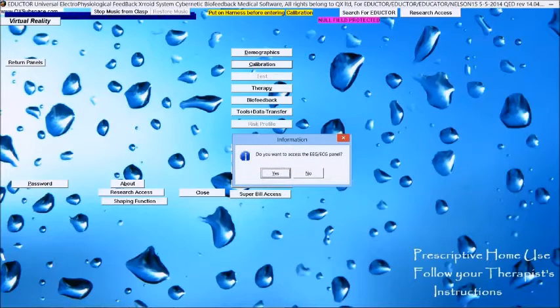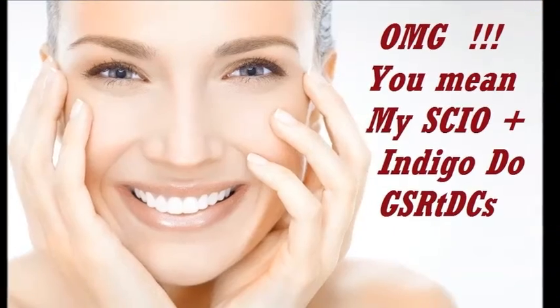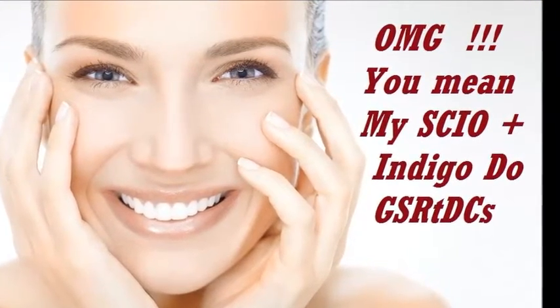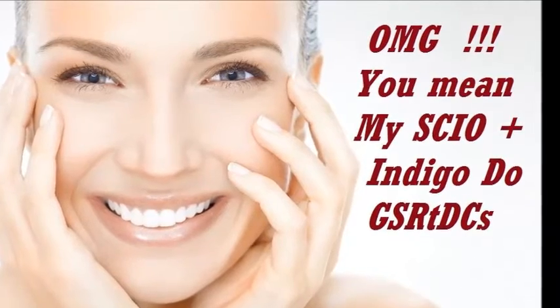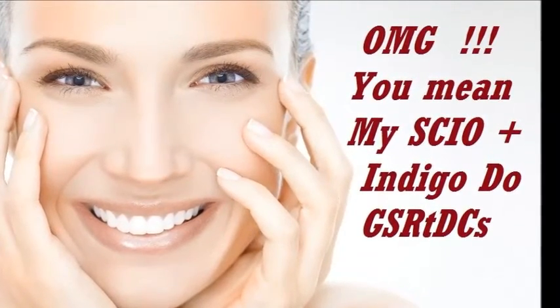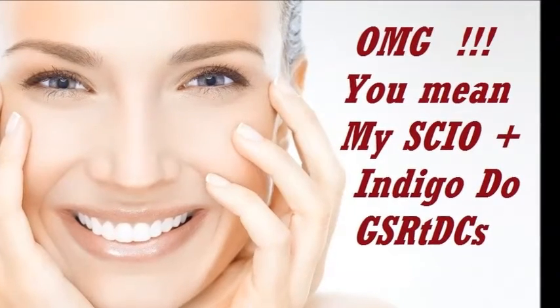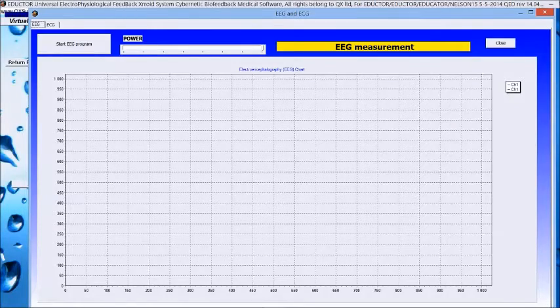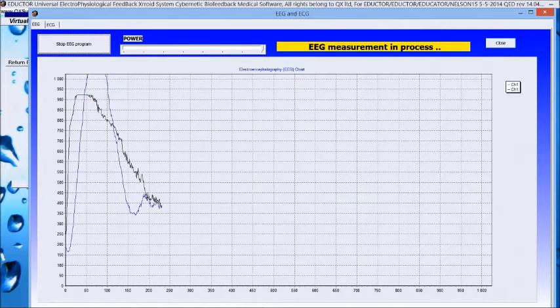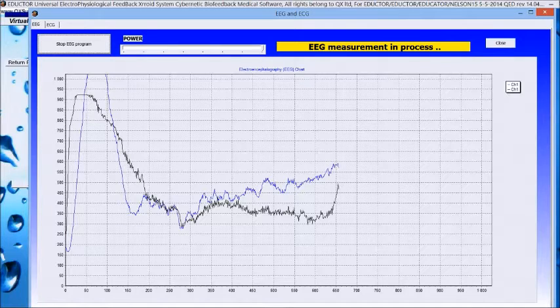Do we want to access the EEG ECG panel? Yes, we select yes. This rather extensive EEG and ECG is only on the Eductor. If you have SCIO and Indigo, you'll have to skip this procedure and move on. Please watch. We are going to start doing an EEG measurement. Start EEG program, click on it to stop, and give it a second to stabilize. Because it is a very, very sensitive EEG, we need to have the patient lay very still. Don't move at all. And let the EEG stabilize.